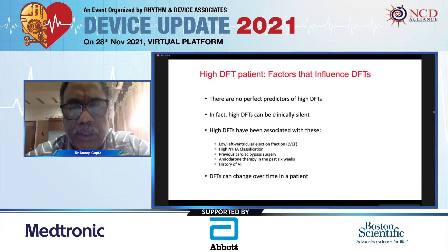So if the scenario is a high DFT, what are the approaches you can take? The most important thing is the RV coil polarity. If it is positive, with the anode in the coil, that is very, very important. It can lower or equal the DFT in 88% of patients. The 12% where it does not work is probably because of noise. It must be changed in the same mode, and there is no side effect.